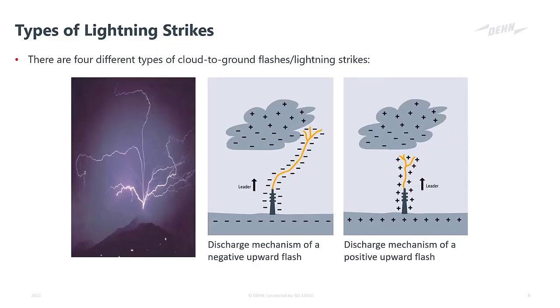The other two types of lightning strikes are upward lightning strikes. This could again be either negatively charged or positively charged depending on the charge on the ground level. But what's different with regards to this is that the charge actually collects on ground level. It goes to a tall structure, and from the tall structure it flashes up out of the tall structure into the clouds. Now, as I said, it's mainly on tall structures, so it would be something like a high-rise building, a telecommunication tower, or a wind turbine. These upward strikes carry very high amounts of energy, charge, and current, because all the lightning current is focused on a single point from the structure from where it flashes, and that is where we have a lot of damage.